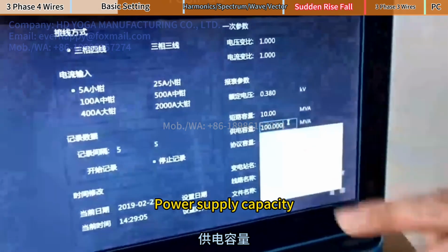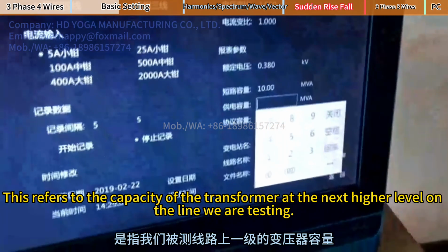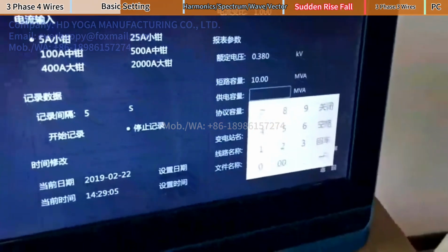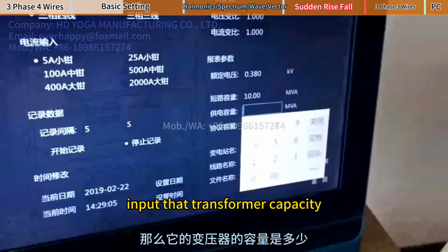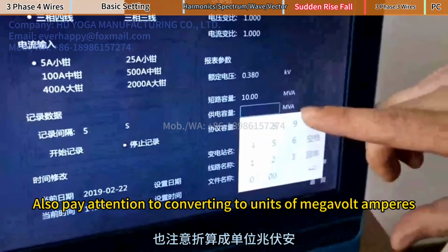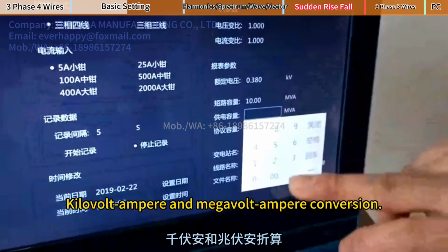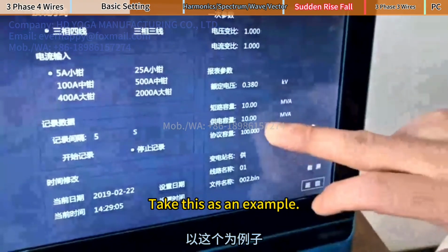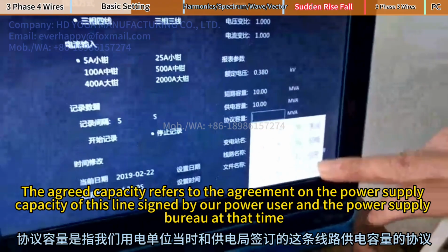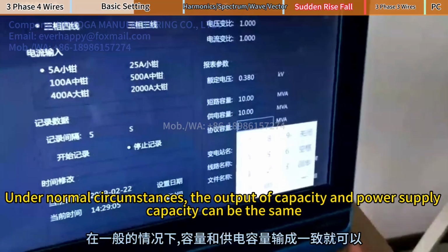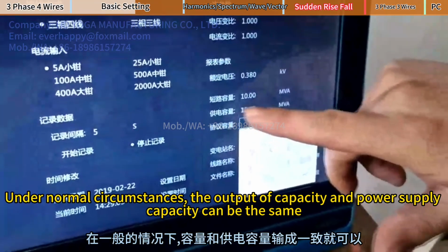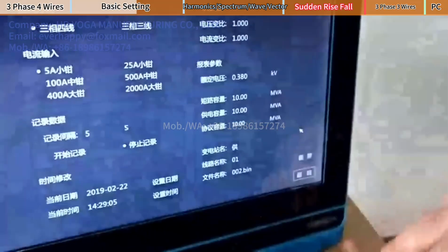Power supply capacity. This refers to the capacity of the transformer at the next higher level on the line we are testing. It refers to which transformer our line outputs from. Input that transformer capacity. Also pay attention to converting to units of megavolt amperes. Let's enter 10 megavolt amps here as an example. The agreed capacity refers to the agreement on the power supply capacity of this line signed by our power user and the power supply bureau at that time. Under normal circumstances, the agreed capacity and power supply capacity can be the same.